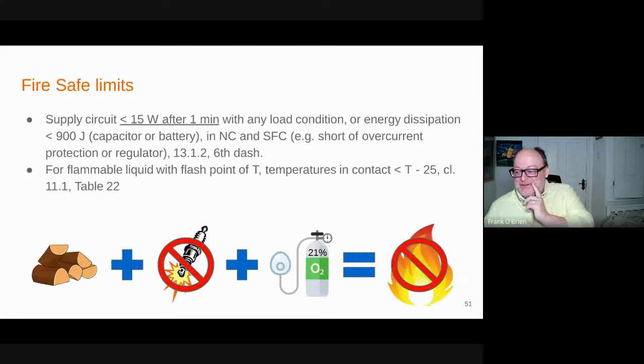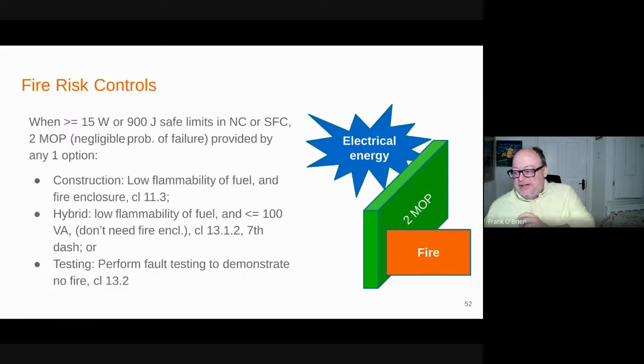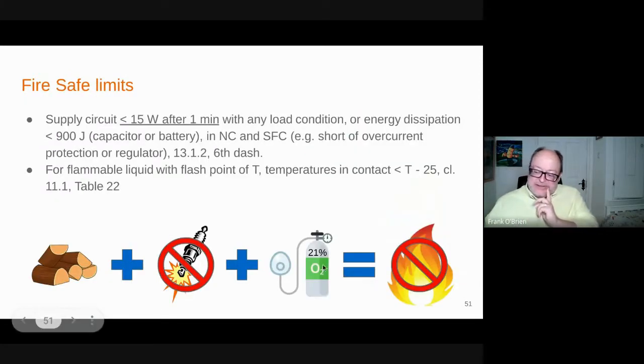All right, so safe limits. I would consider the 15 watt after a minute to be inherently safe. There can't be a fire. There's no ignition source, if you will. So I'll mention that in the safe limit area that I'd normally talk about. The other thing is this 25 less than the flash point for flammable liquids. That's sort of a safe limit as well. But the concept we'll continuously try to understand is you need fuel, you need an ignition source, you need oxygen, and you're going to have a fire. And so with safe limits, we're trying to remove the ignition source. Okay.